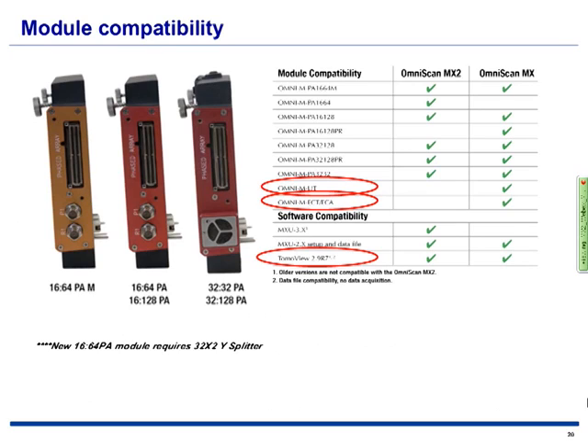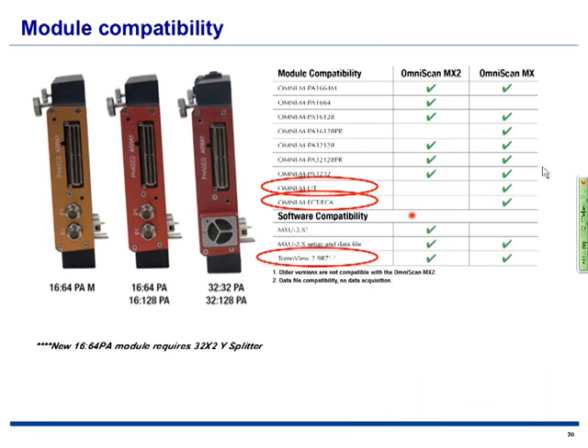Module compatibility. Eddy current modules are not supported by the MX2 and will not be in the future. UT modules, like the 2, 4, and 8 channel OmniScan UT, are not supported now, but will be in the near future. All other modules, standard in the Olympus catalog, are compatible with both the MX and MX2 base units.